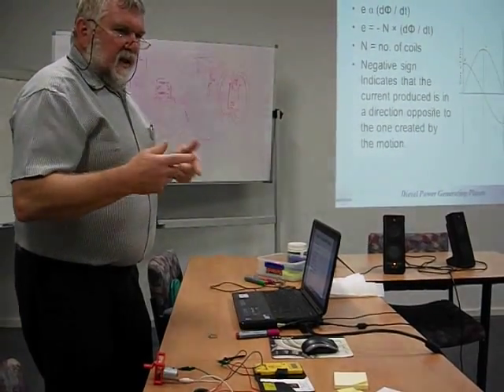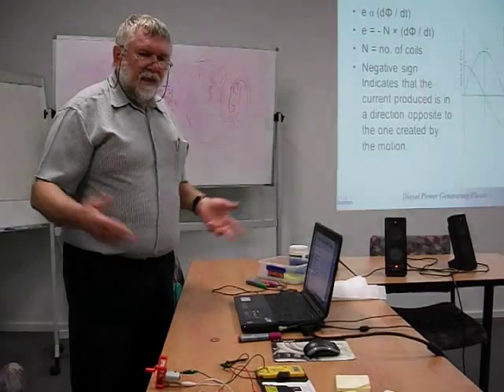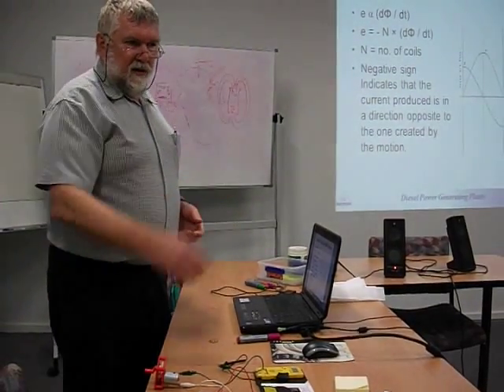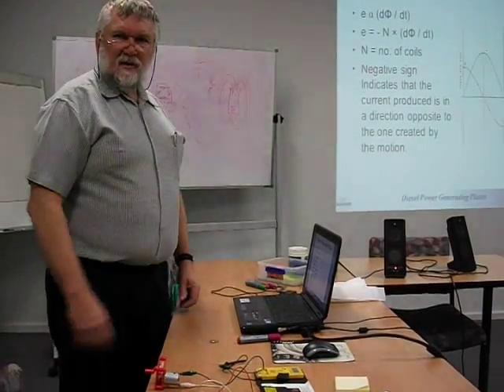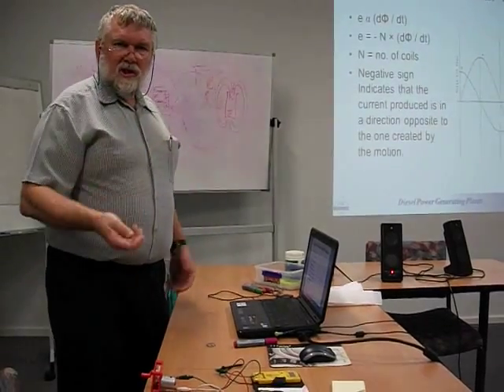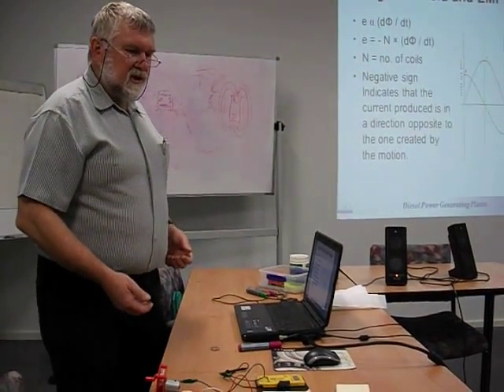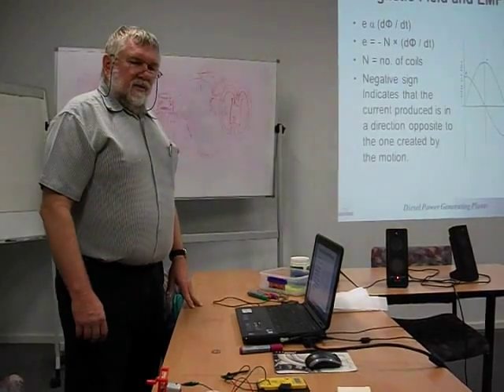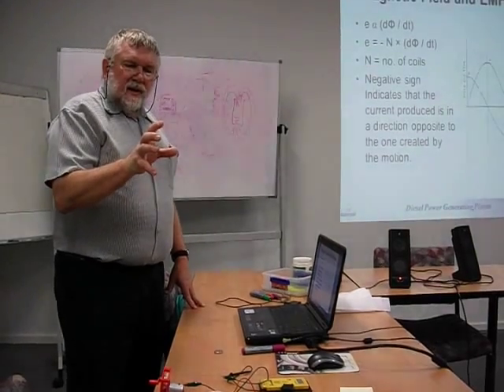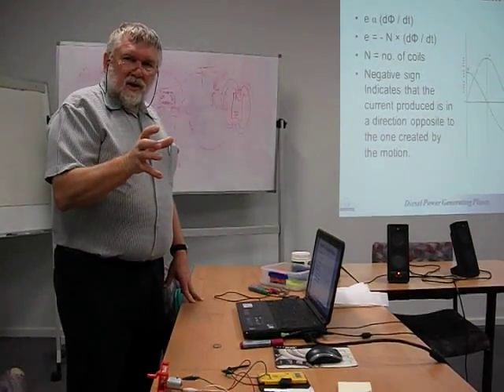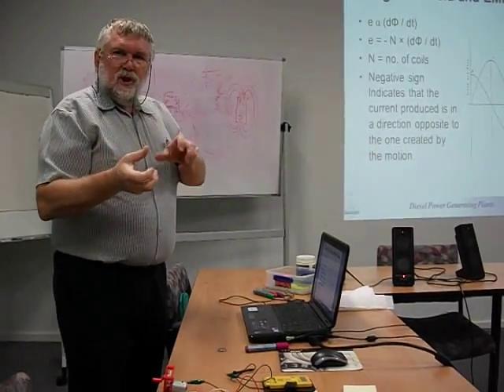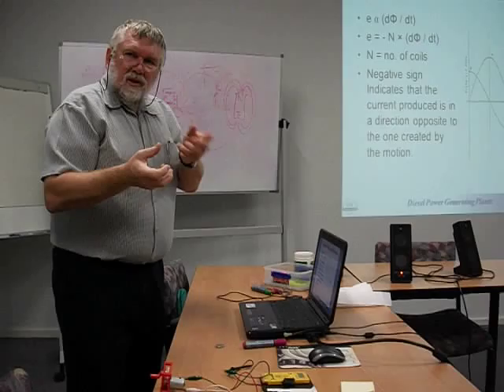So that explains why if you go into a spares warehouse and there's a generator there, and you can turn it, it's got a six-inch shaft on it, a 150mm shaft on it. And you can turn that by hand quite easily. So you think, well, why is it hooked up to a 20-cylinder diesel engine? The reason is that as you turn that and put a load on it, the currents developed are strong enough to generate a magnetic field that actually pushes back against the rotation.